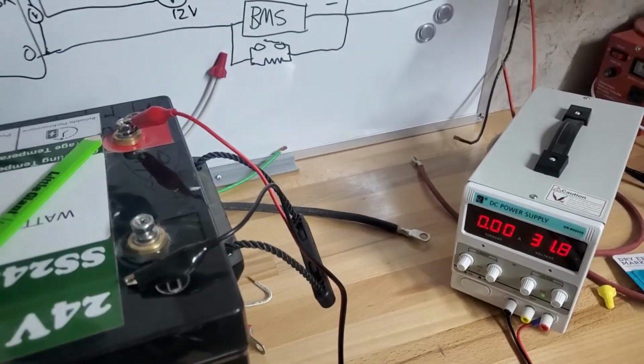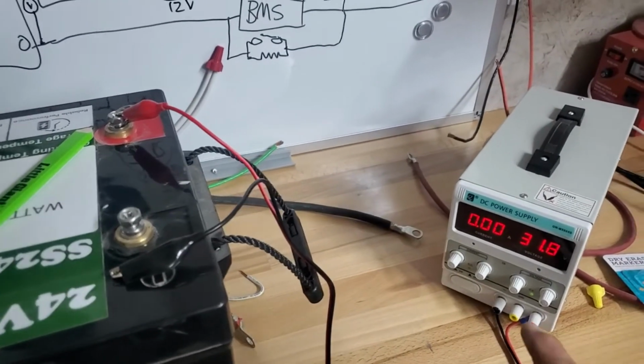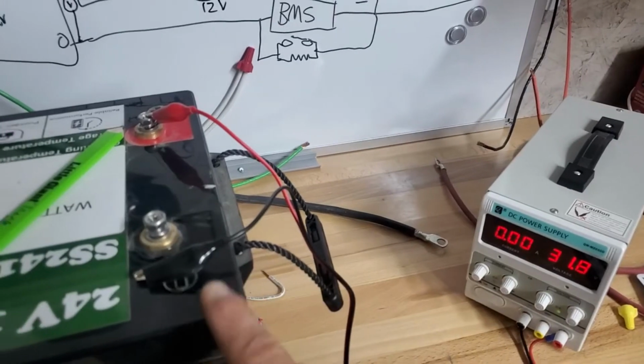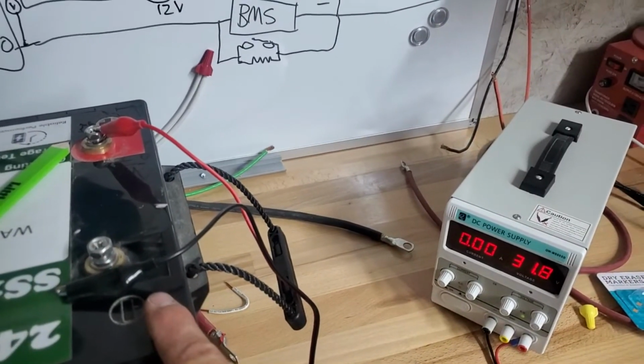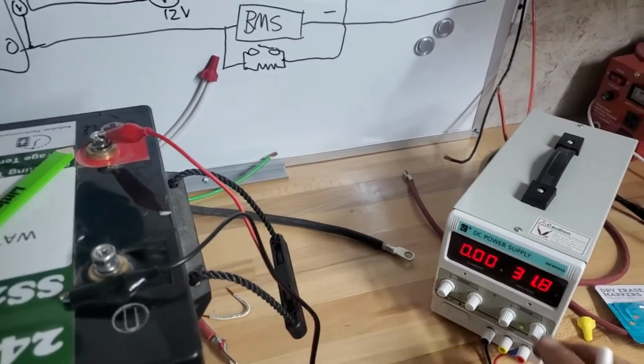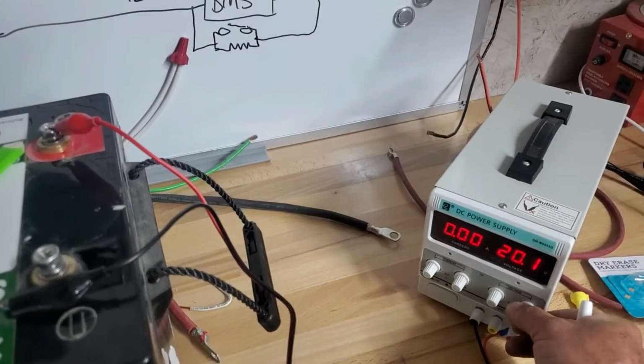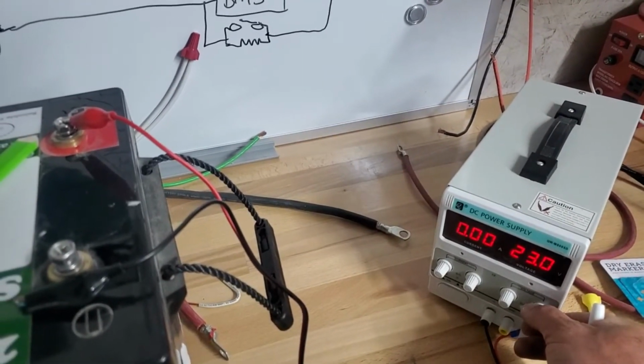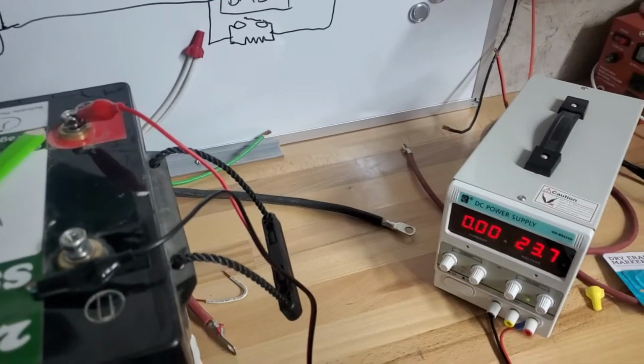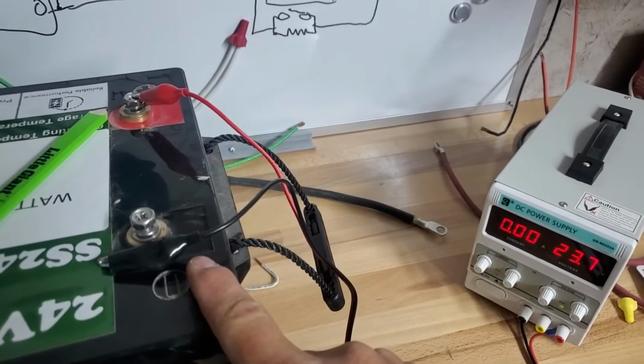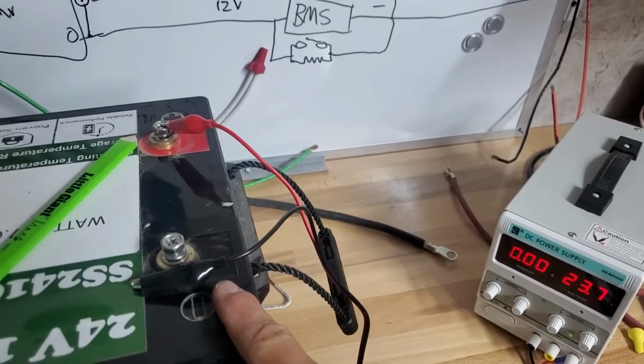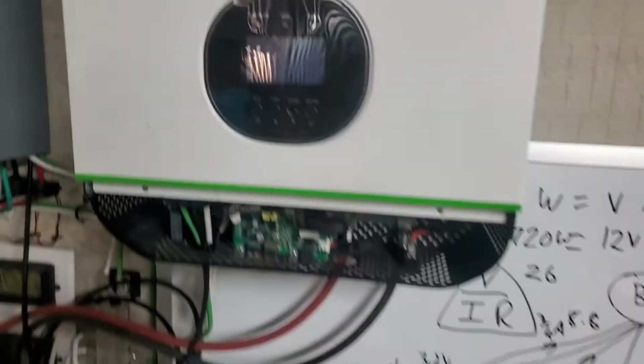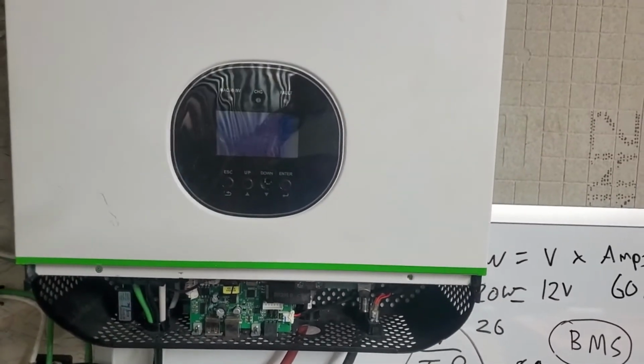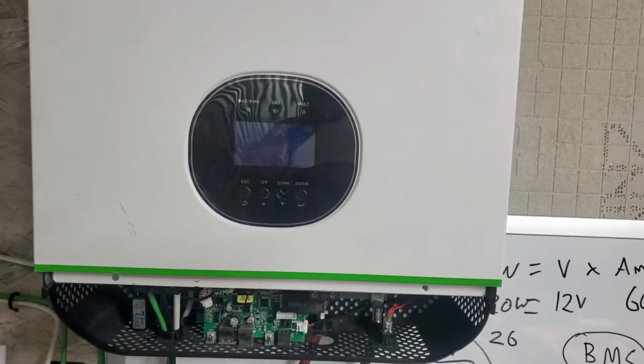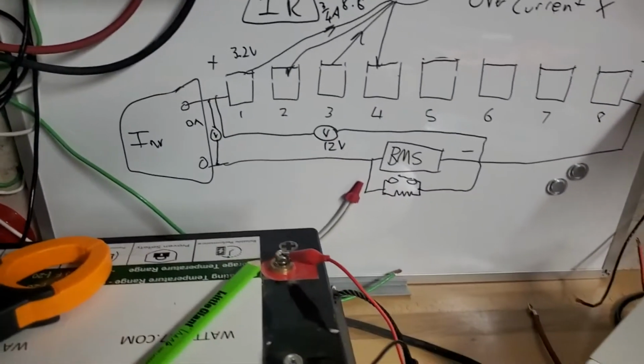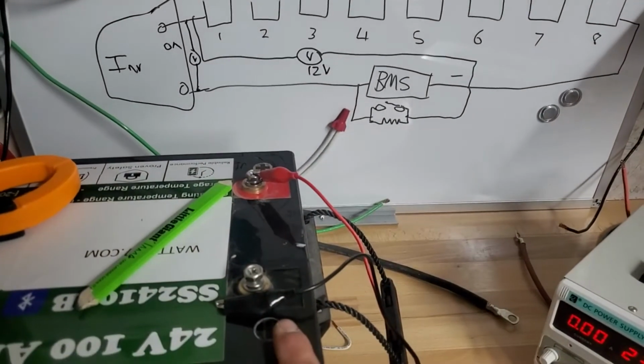Here's another point I want to bring out. While your inverter is trying to charge this battery to 26 or 27 volts and you've got it set to 28 volts, the moment it reaches higher than the over voltage setting inside the BMS, the battery simply goes open circuit, which usually throws a fault code on the inverter, like fault code 8, high voltage, and then it won't start charging the battery again until it's fully discharged the next day.